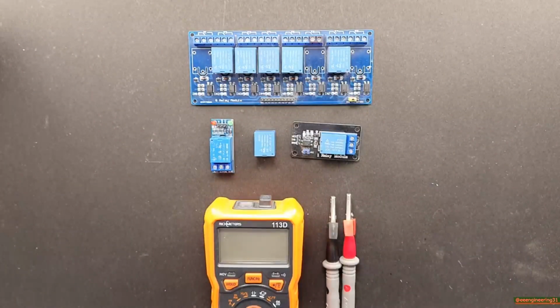Now let's check the common failure causes of relays. Relay troubles usually involve the switching contacts: corrosion from age and oxidation, as well as pitting from arcing when large currents are switched, cause resistance or flaky contacts. Sometimes the contacts will weld together, not wanting to open back up after the power is removed from the coil. This condition can be caused by arcing in the contacts, making them stick to each other, and by weakening of the spring which is used to pull the plate away from the iron core.